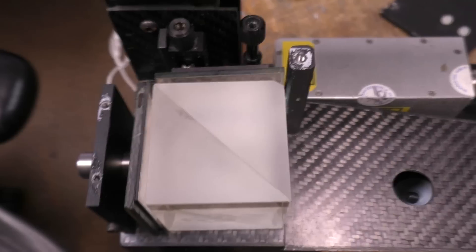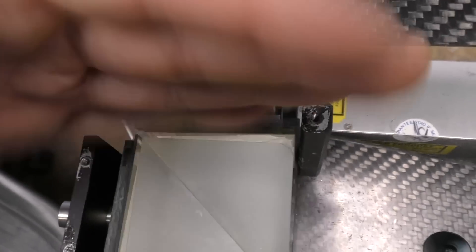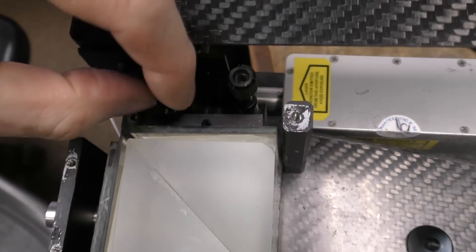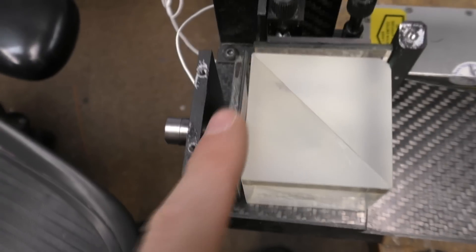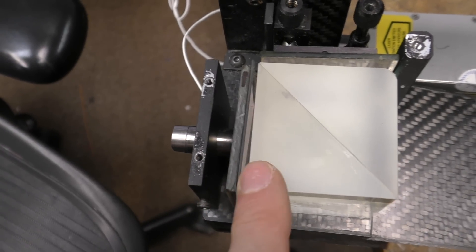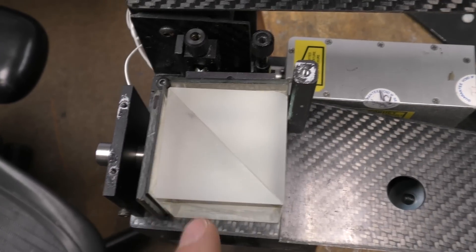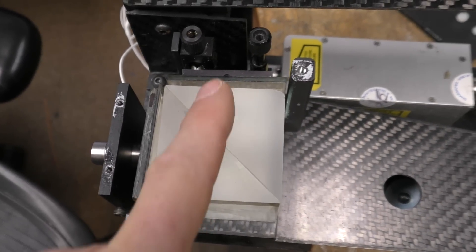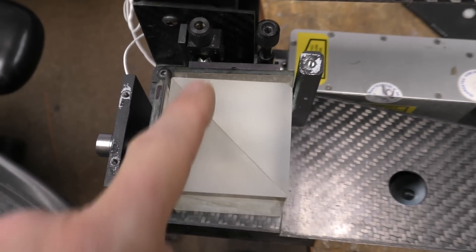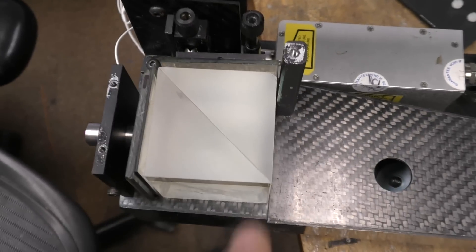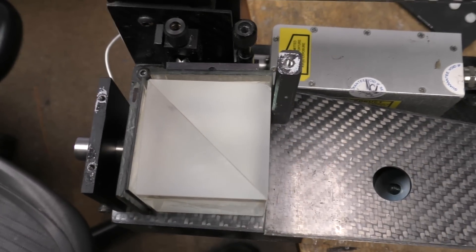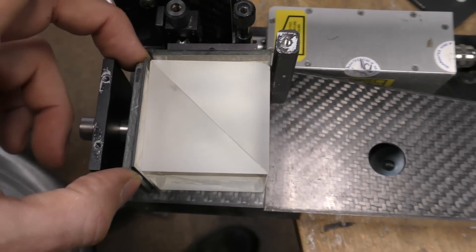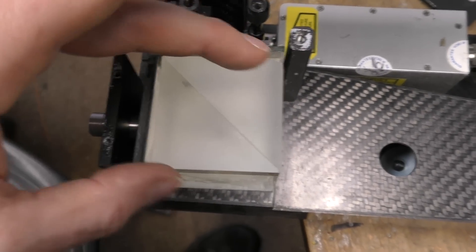Just taking the top cover off, it makes it a little bit clearer what's going on. We've got this beam splitter and there's two mirrors. There's this one which is fixed but adjustable in X and Y tilt by these two adjusters - these are accessible from the outside. The second mirror is mounted on the piezo actuator. We've got one direct light path which goes in, bounces off that mirror, then goes this direction. Then the other one which comes in goes off this mirror and then goes straight into the camera. This piezo is generating a difference in the distance the light's traveling through those two paths.